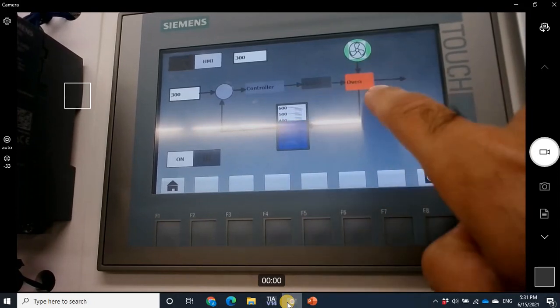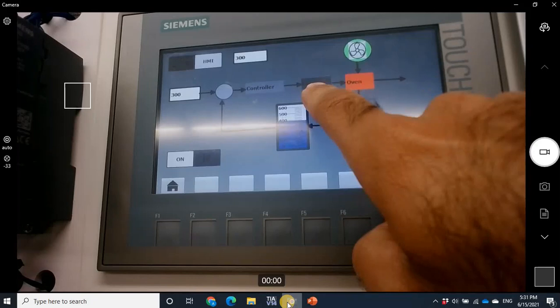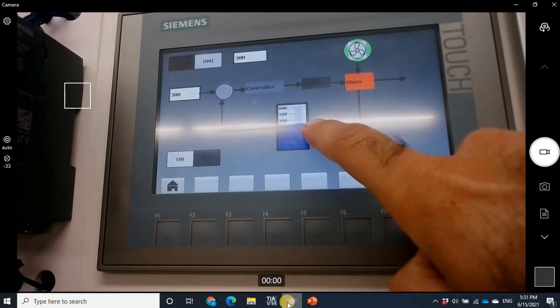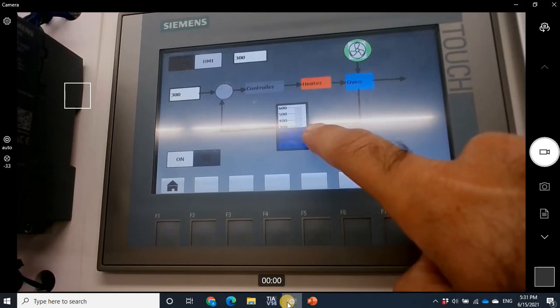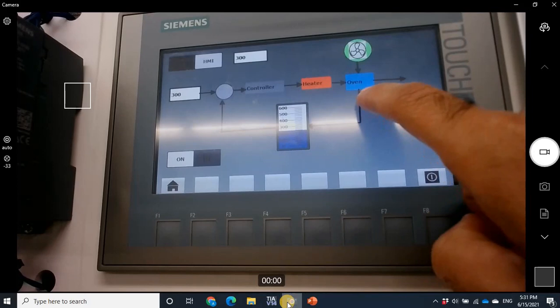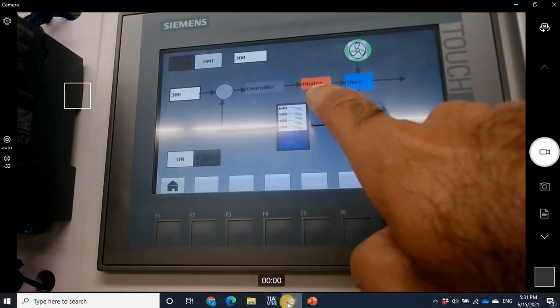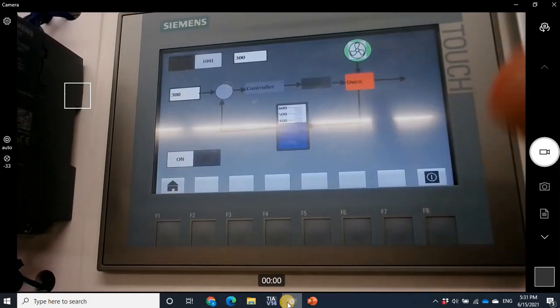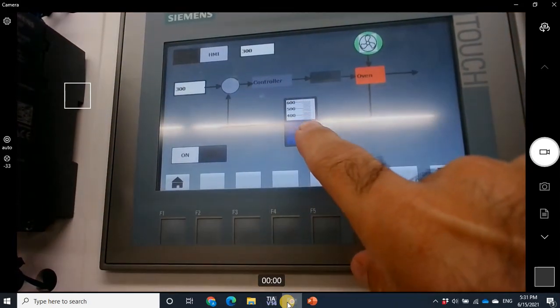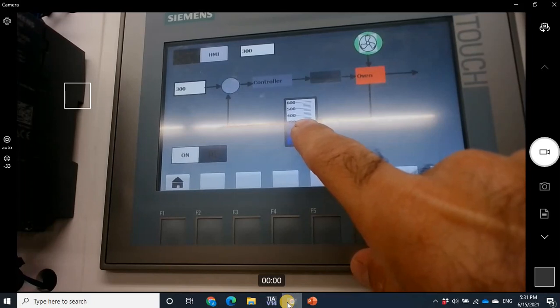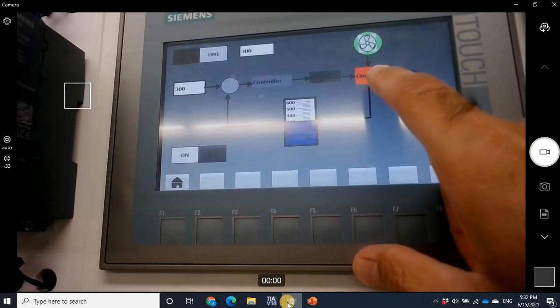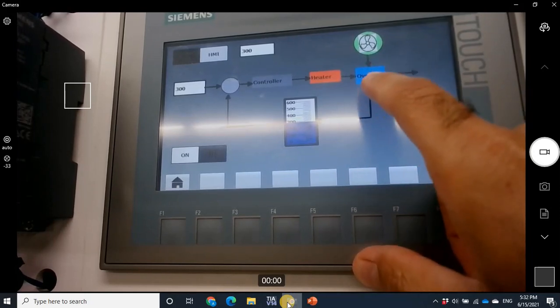The temperature is approximately 400, so the oil is hot and shown in red, and the heater is on. When the heater is off and the fan is on, the temperature decreases. You can see that when the temperature is low, the oven becomes blue meaning it's cold and the heater turns on — so that works properly. However, when the temperature is around 300 (the set point), the oven should turn green, but it switches from red to blue without going green.